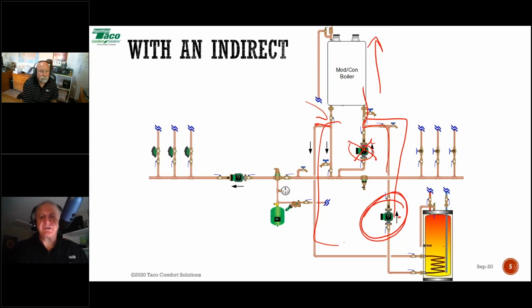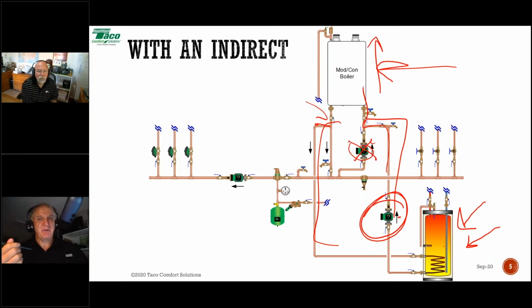When sizing this circulator, you have to account for the flow rate needed for the indirect. That could be anywhere from 8 to 10 gallons a minute. So we have to take into account the flow rate needed for the indirect to make our domestic hot water. We have to take into account the head loss of the heat exchanger in the indirect. All right, that has to be added, as well as the head loss through the heat exchanger in the boiler at the flow rate needed for your indirect. So we're going to need to make sure we understand what those numbers are.